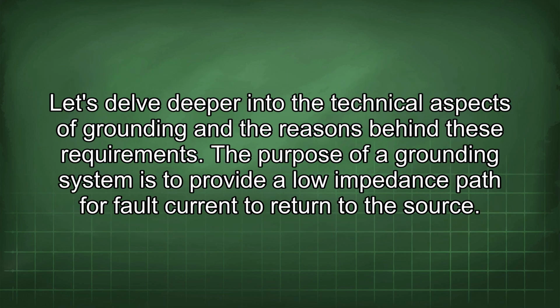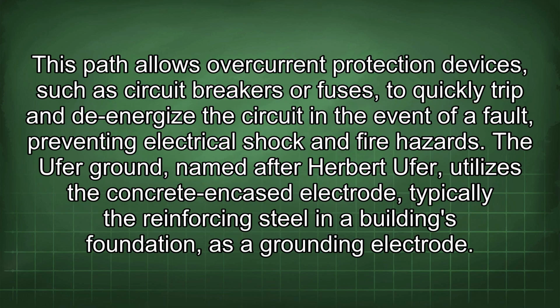Let's delve deeper into the technical aspects of grounding and the reasons behind these requirements. The purpose of a grounding system is to provide a low impedance path for fault current to return to the source. This path allows overcurrent protection devices, such as circuit breakers or fuses, to quickly trip and de-energize the circuit in the event of a fault, preventing electrical shock and fire hazards.